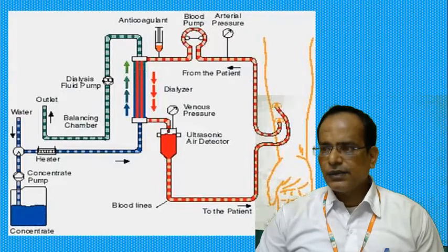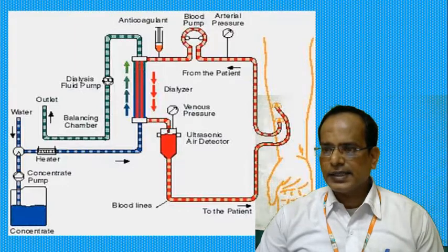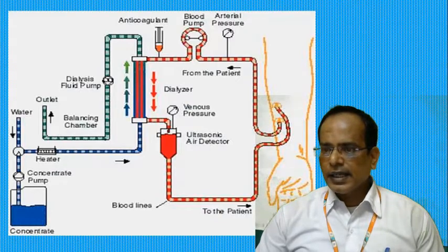The use of a ground fault interrupter, called a GFI, is recommended because the dialysis fluid can get into some of the electrical circuits and create ground line currents from the case in excess of the 5 milliamp safe level.